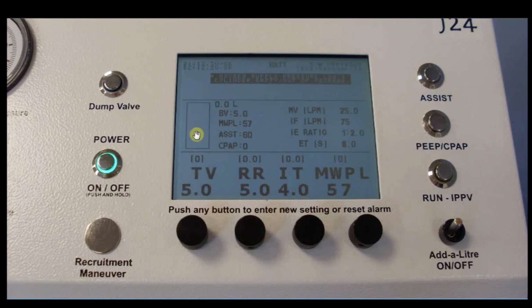While we're talking about this now, this ties in quite nicely with this add a litre feature or add a litre button. When the switch is up, as it is now, it's in the on position, and if we had oxygen connected and there was any slight pressure in the system, then the machine would automatically add a litre of oxygen through the vaporizer to put some more gas into the system.